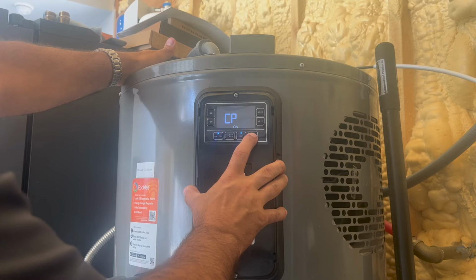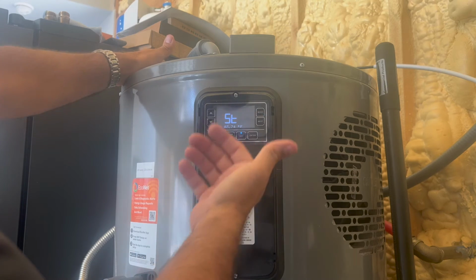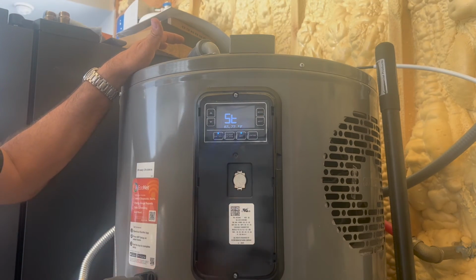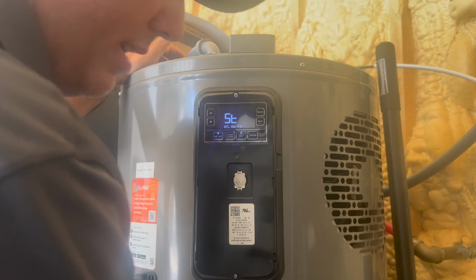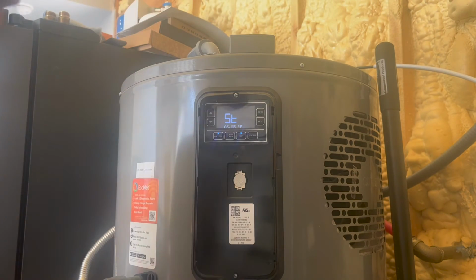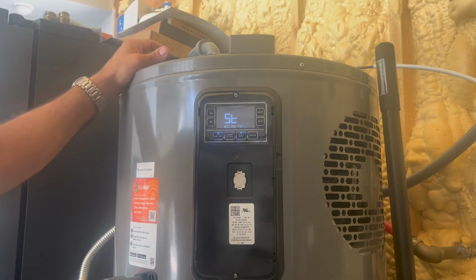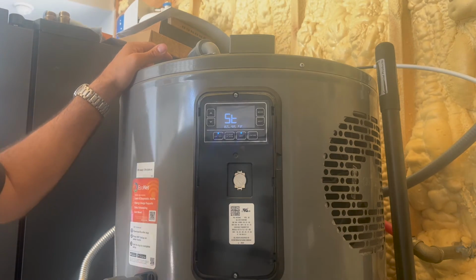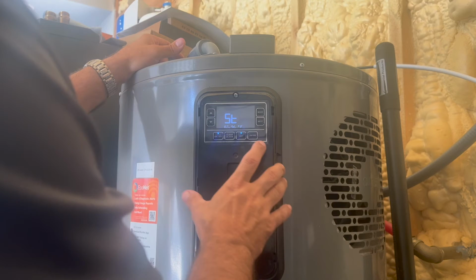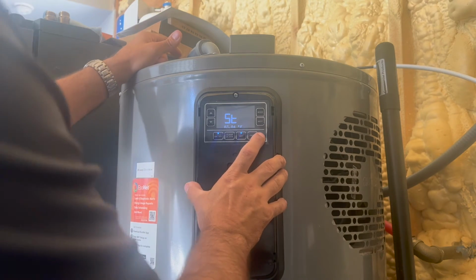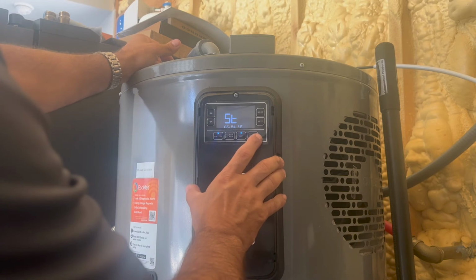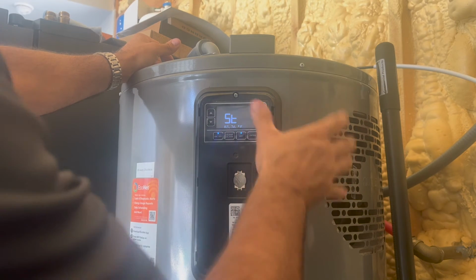Ambient's going to remain the same because it's not getting any cooler in this garage. And we saw the suction temperature go down into the 60s. Those are good. I got hot coolant going down. I've got cooler coolant coming back up. Maybe I should say Freon, whatever you want to consider it. Nice and cool, pulling a lot of heat out of the air, sending it down into the water heater. Now, if we see numbers like that, we can suspect that this part is working.